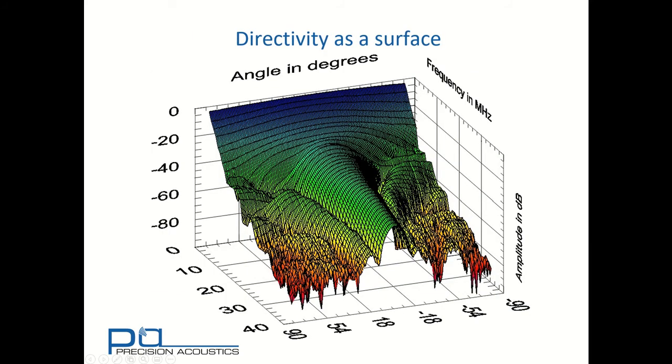We can also consider directivity as being a surface. This allows us to see the variation both as a function of angle of incidence and frequency. This is the directivity surface for the 0.2 millimetre needle hydrophone we were looking at previously. We can see at low frequencies we have a very broad response, but as frequency starts to increase we see a very dominant main lobe, and then secondary lobes, and between the primary and secondary lobes we have nulls. At very high frequencies we can start to see the emergence of tertiary lobes as well.